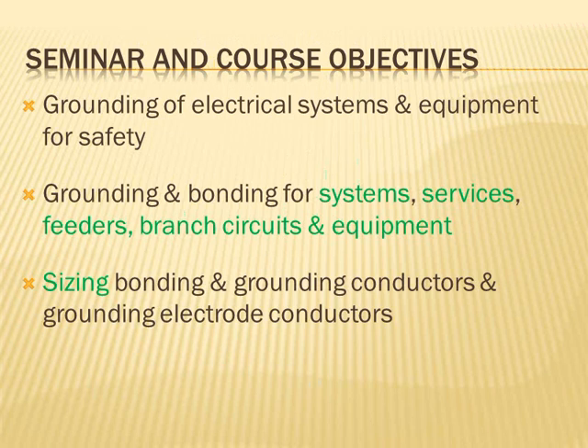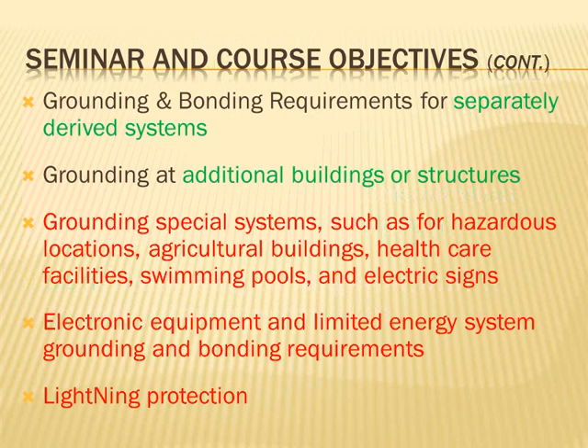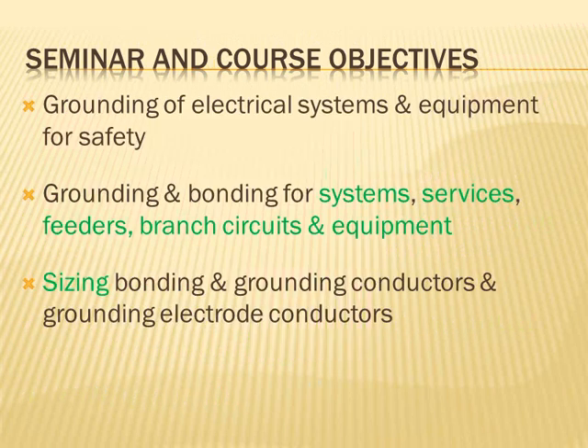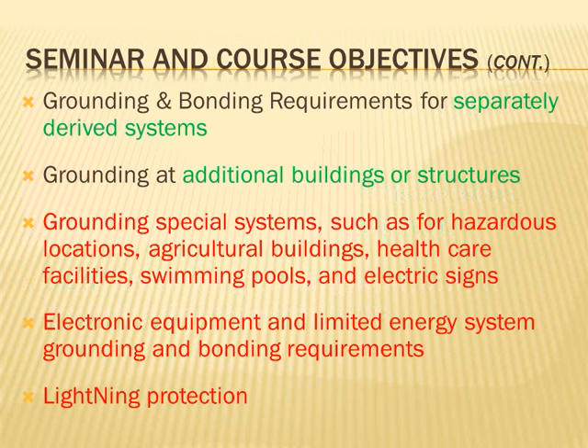So in reality, that book talks about, for the most part, 3 different things. Start with your system, grounded or non-grounded, done. Go to your service panel, the main panel. Then you have to do grounding and bonding, regardless if the system is grounded or ungrounded. And then you're done here, then you go to your feeders and branch circuits, and you have to do grounding and bonding at the panels and so forth. So these are what the sheet hopefully covered for you guys. And of course, sizing it. You saw how we sized the whole thing, and the sheet that I gave you sizes all these systems.